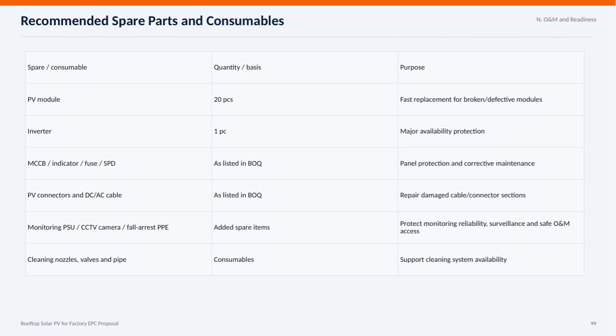On this slide, we focus on the recommended spare parts and consumables essential for the rooftop solar PV system in our factory EPC proposal. First, having 20 spare PV modules ensures we can quickly replace any broken or defective panels, minimizing downtime. We also suggest keeping 1 spare inverter on hand, as this acts as a critical backup to maintain system availability. For panel protection and maintenance, items like MCCBs, indicators, fuses, and surge protection devices should be stocked according to the bill of quantities.